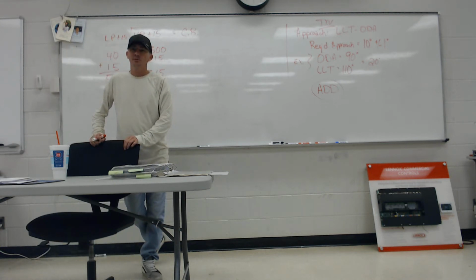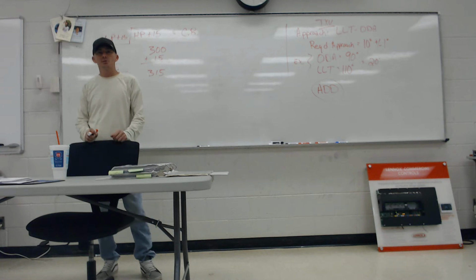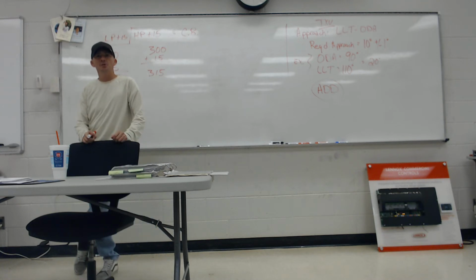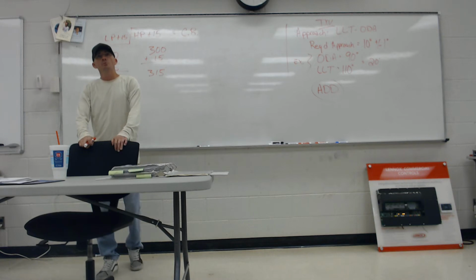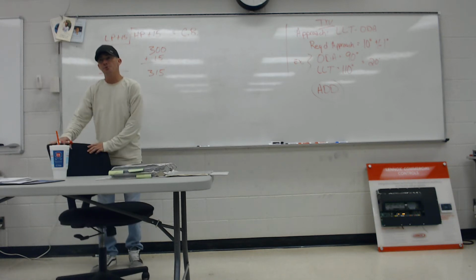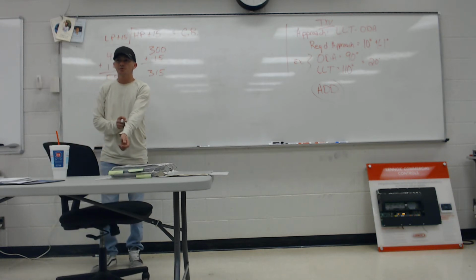Oil temp. Everyone remember how to solve for oil temp? Discharge temperature plus 75. Yeah, clamp on the discharge line. So it's not a pressure temperature, sorry, discharge temperature. Yep. Clamped on the discharge line, add 75 to it. Mineral oil, well, 300 is critical, 315 is breaking down, and you're going to lose a compressor.